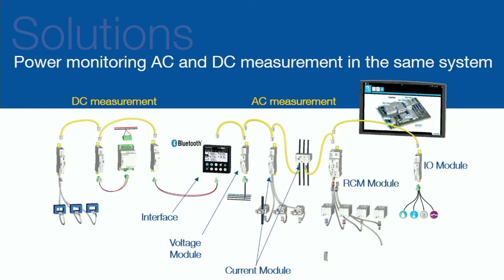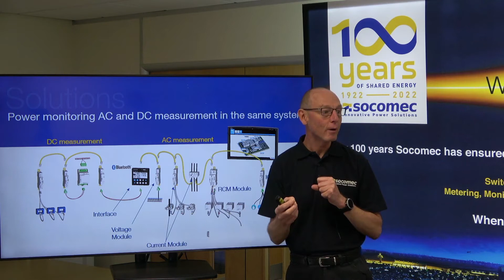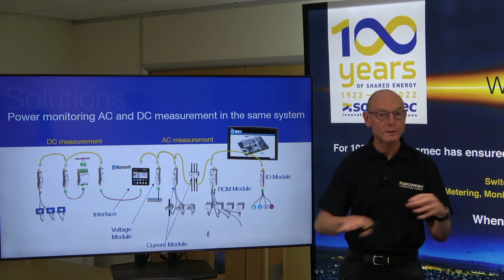This is where we're able to monitor the installation such that we are able to detect if we've got a residual current fault, and the ability to continually monitor. So if you have that as part of your installation and your monitoring, it means that you don't have to do the annual or 5-yearly tests, because the standard was updated to say that if you monitor constantly, you don't have to do those. Which is a big cost saving, I guess.